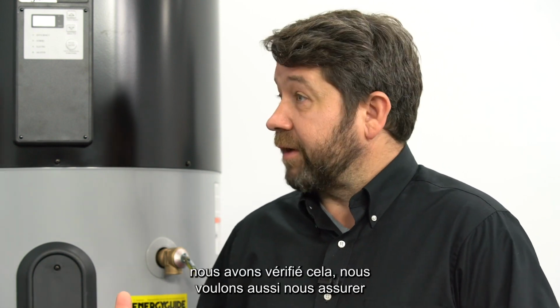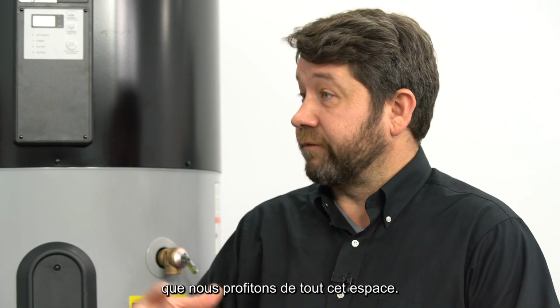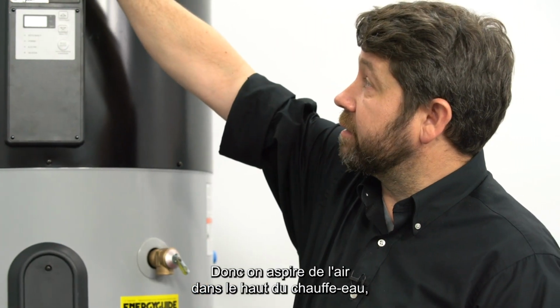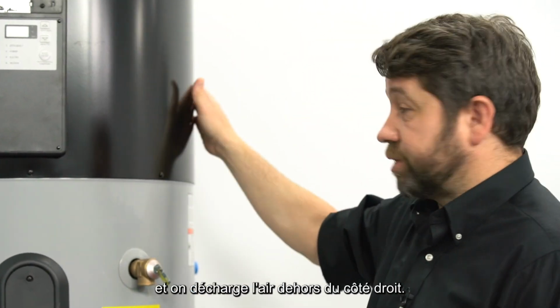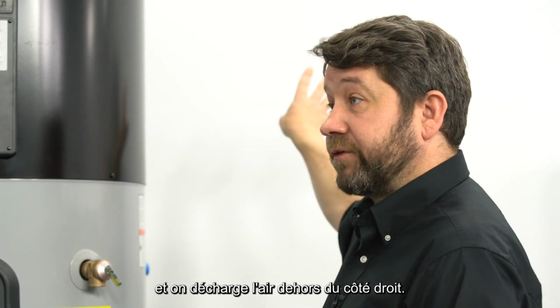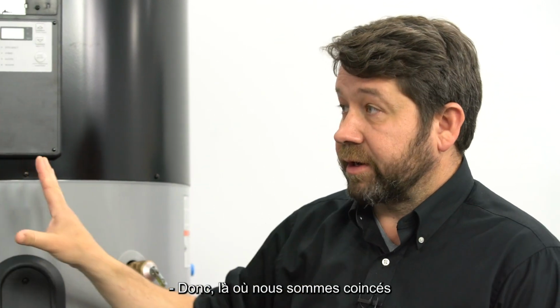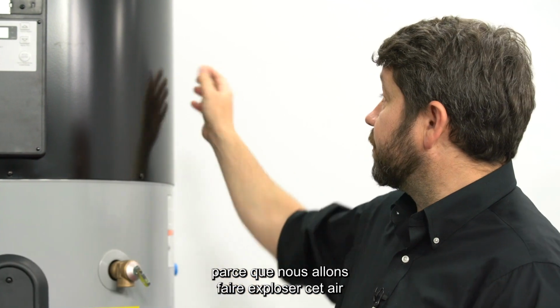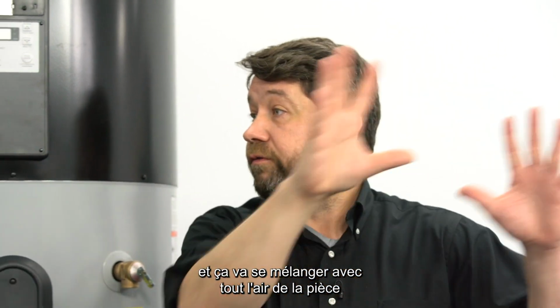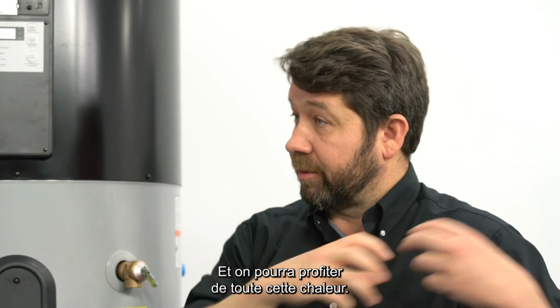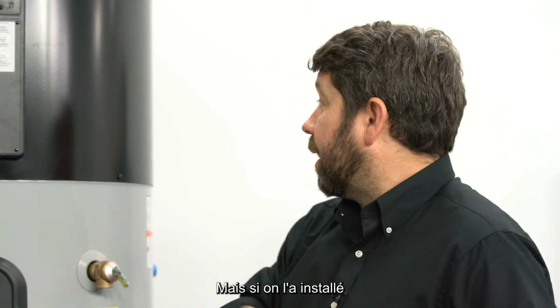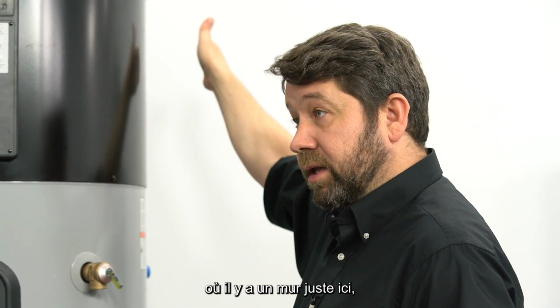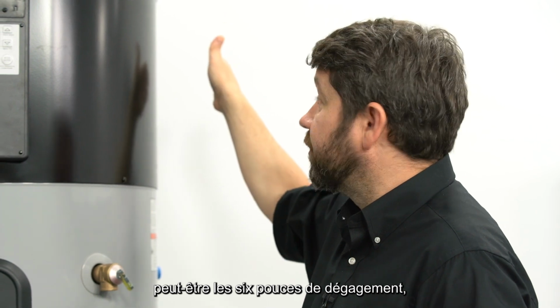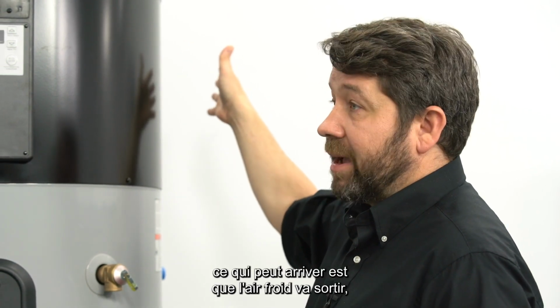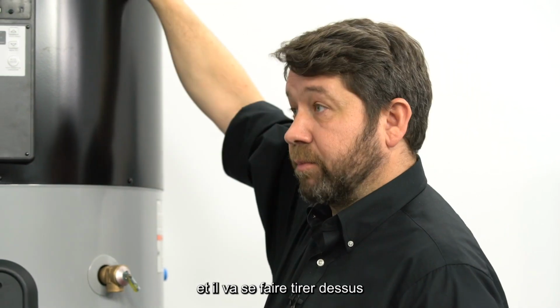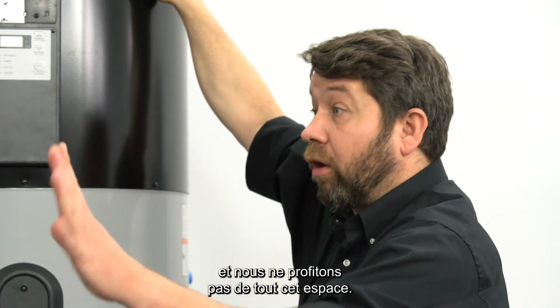Right. So once we've verified that, we also want to make sure that we're taking advantage of all of that space. So we're pulling air into the top of the water heater, and we're discharging the air outside from the right side. Where we've got it in this corner is a really good application, because we're going to blow this air out and it's going to mix with all of the air in the room and then come back, and so we'll be able to take advantage of all that heat. But if we've got this installed where there's a wall right here, maybe the 6 inches of clearance, what can happen is that cold air is going to come out, it'll hit that obstruction, and it'll just get pulled right back in, and we don't take advantage of all of that space.